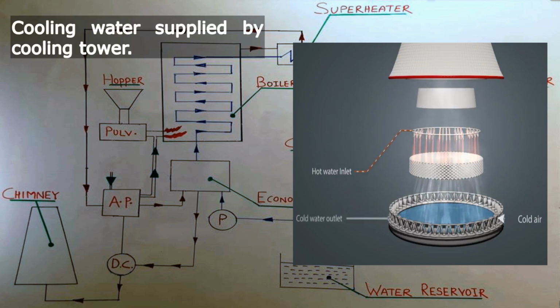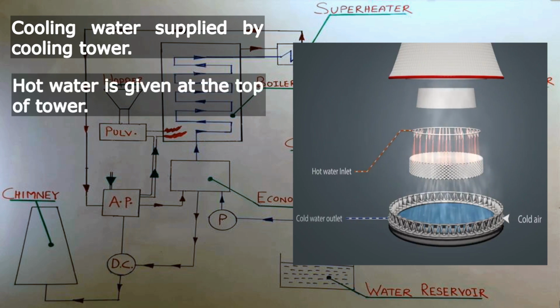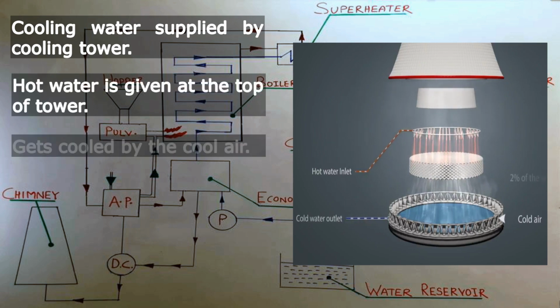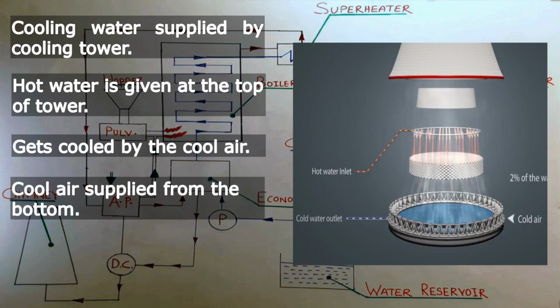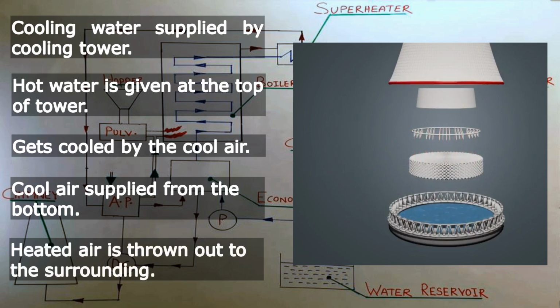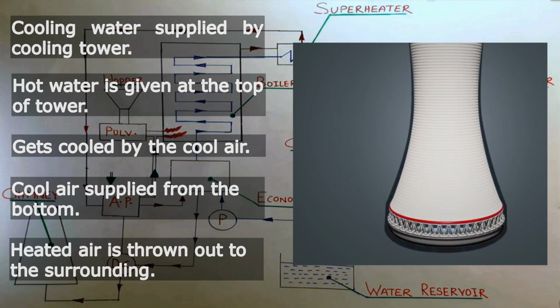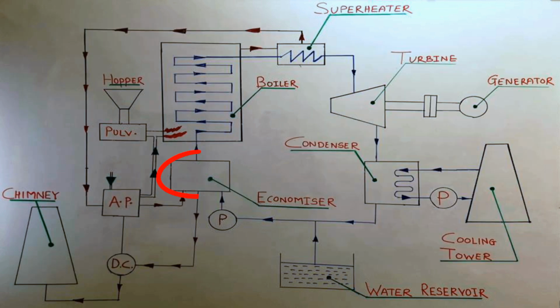The resultant heated water from the condenser is given at the top of the cooling tower. This heated water gets cooled by the cool air passed from the bottom of cooling tower. The heated air is thrown out to the surrounding from the top of the cooling tower. Now the next very important element is an economizer.